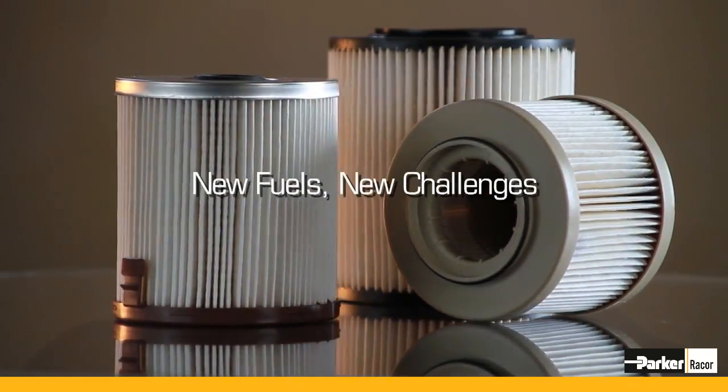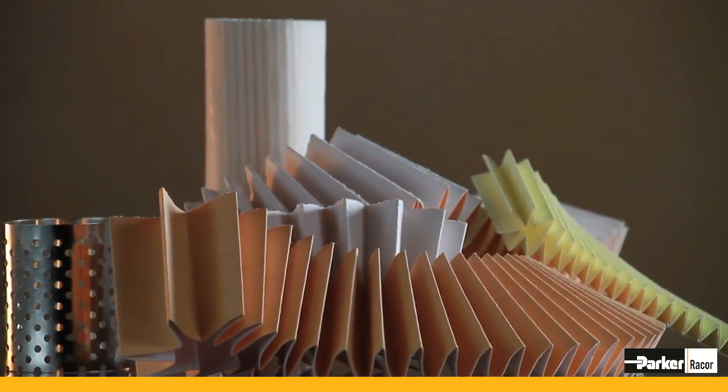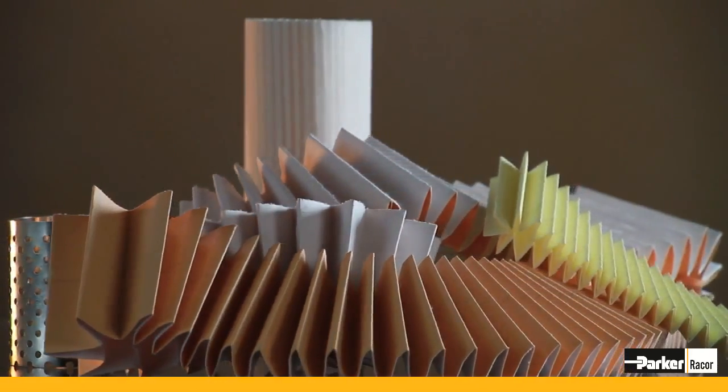With new fuels today, the differences between water and fuel are not as clear anymore. Now you add surfactants, lubricity additives, anti-wear additives, or biodiesel to that, you shake up that same mixture, and the oil and water are very compatible with one another. To effect separation of fuel and water with today's fuels, where there's a lot of surfactants, the water is a smaller particle size and it's much more stable due to the presence of surfactants adsorbing onto the surface of the water drops. In order to separate that, the most effective way is to present hundreds of square meters of surface area. And essentially anything on Earth can be separated if you have enough surface area.